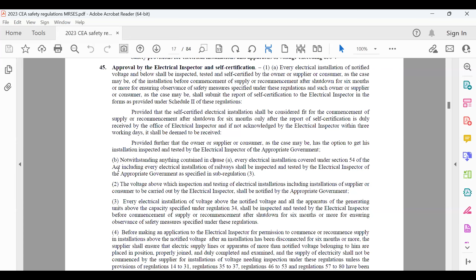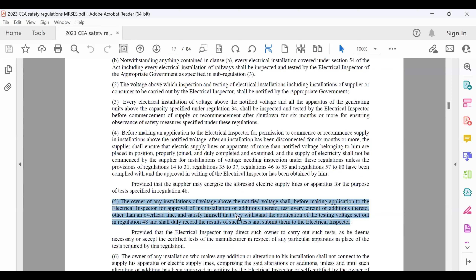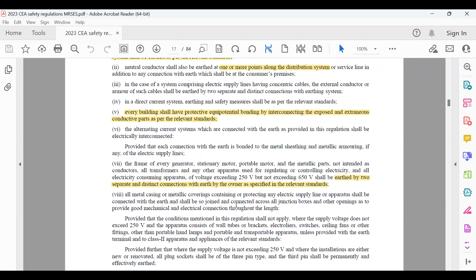Actually, regulation 45 applies to installations above 650 volts. But there is another regulation, I think it is 31, which requires the consumer to give the test report of the installation to the supplying company, and that applies to LT installations also. The format of this test report, I think given under Form 4, needs to be looked at from the point of view of type of installation, whether single phase or three phase.